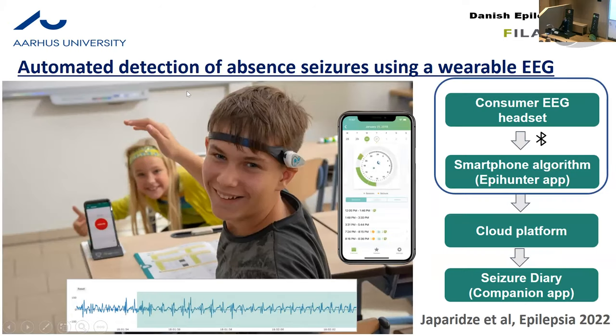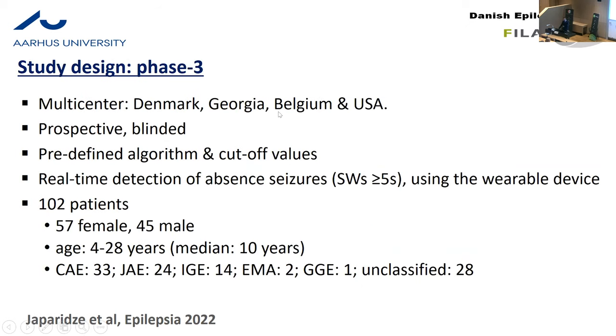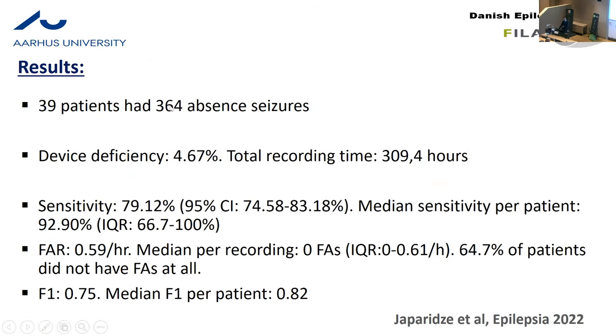This is another seizure type — absence seizures. Here you can see a wearable EEG device with dry electrodes, but here we used a different approach: we trained an AI model to catch these absence seizures. We validated it in a phase three study — prospective, multi-center, 102 patients, 39 of them with seizures, altogether more than 300 absence seizures. The sensitivity of this gadget with the algorithm was around 80% for all seizures, and the median sensitivity per patient was 92%, with a false alarm rate of 0.6 per hour.